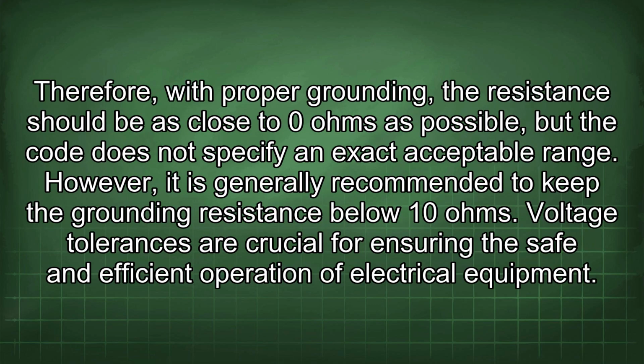Therefore, with proper grounding, the resistance should be as close to 0 ohms as possible, but the code does not specify an exact acceptable range. However, it is generally recommended to keep the grounding resistance below 10 ohms.